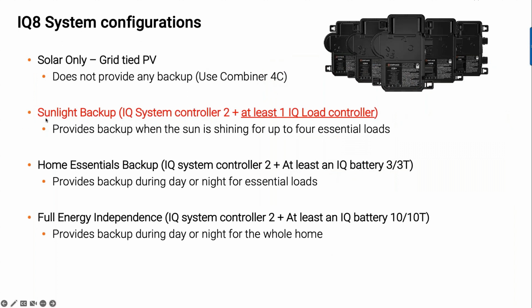I want to spend a little time talking about a specific configuration of IQ8 in backup, and that's sunlight backup. There are several different ways to install IQ8, and one of those ways is in a sunlight backup configuration. We're going to use IQ8 microinverters, which are unique because they can grid-form. It is a multi-mode inverter. IQ8s can be installed in a configuration where, if the utility fails or goes out, they can start forming their own utility grid signal, given that you've got sunlight on the solar panels feeding these microinverters. They will create a grid and continue to run loads within a home in the absence of utility.